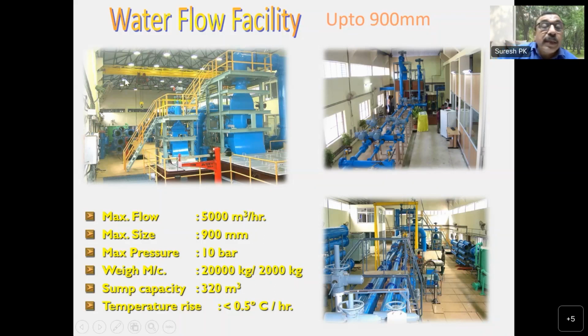This is the system in FCRA in the water flow lab. As I have been telling you, the diverter system is basically very simple. You have a flow coming from the upstream of the meter here, and it passes through the meter and comes to the diverter. It normally goes into the sump which is seen here. Whenever you want to make a measurement, you actually divert the flow into the weighing tank.